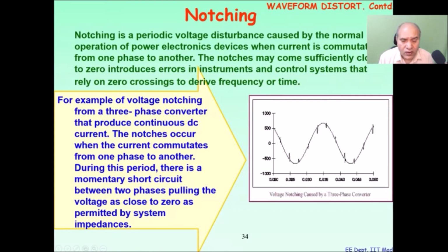Then another criterion for waveform distortion was notching, if you remember. Notching is the presence of notches in the voltage or current waveforms. Mostly the notches appear in the voltage waveform because of the sudden change in currents on the load side. For example, if you have a rectifier circuit, the rectifier switches 6 times over a cycle in a 3-phase system, and these 6 times are reflected here. If you see, this is 1, this is 2, 3, 4, 5, 6. Again 1, 2, 3, 4, 5, 6. So each notch represents the switching operation of the converter.